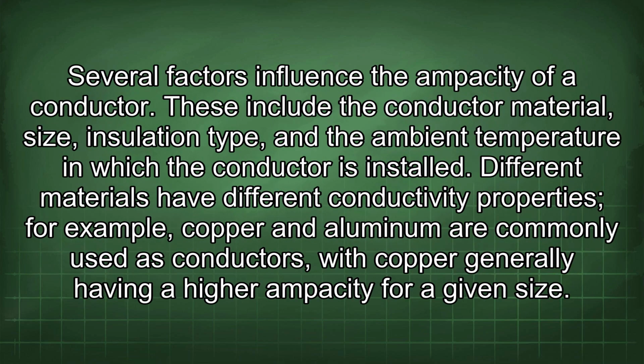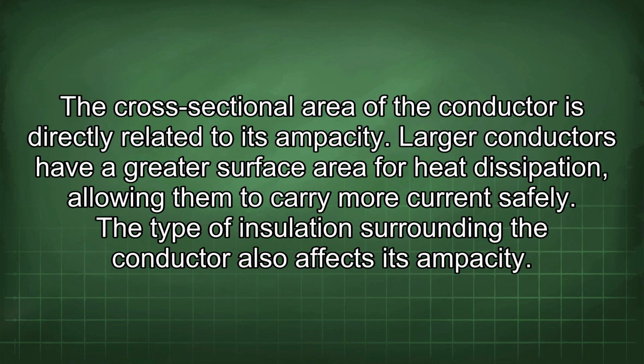Several factors influence the ampacity of a conductor. These include the conductor material, size, insulation type, and the ambient temperature in which the conductor is installed. Different materials have different conductivity properties. For example, copper and aluminum are commonly used as conductors, with copper generally having a higher ampacity for a given size. The cross-sectional area of the conductor is directly related to its ampacity. Larger conductors have a greater surface area for heat dissipation, allowing them to carry more current safely.